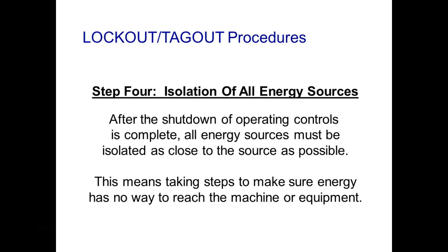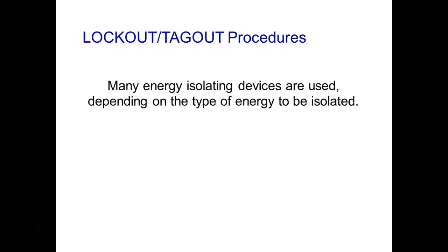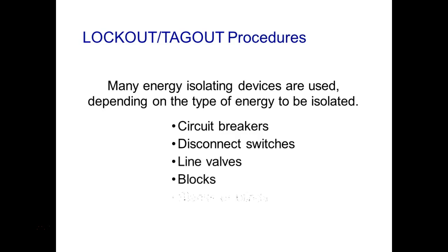After shutting down of operating controls is complete, all energy sources must be isolated as close to the source as possible. This means taking steps to make sure energy has no way to reach the machines or equipment. Many energy isolating devices are used depending on the type of energy to be isolated. Circuit breakers, disconnect switches. Y'all know what a disconnect is, right? Yeah, disconnect. So y'all know what disconnects are now, right? And this is usually where we try to lock them out at, is the actual disconnect.